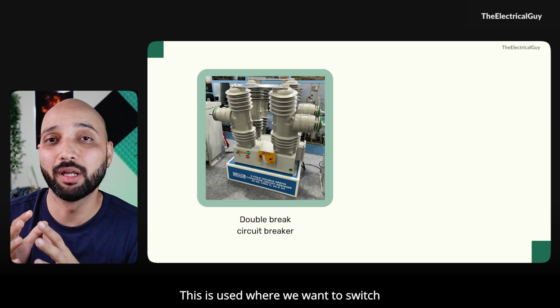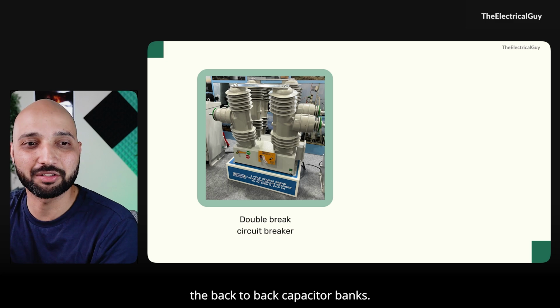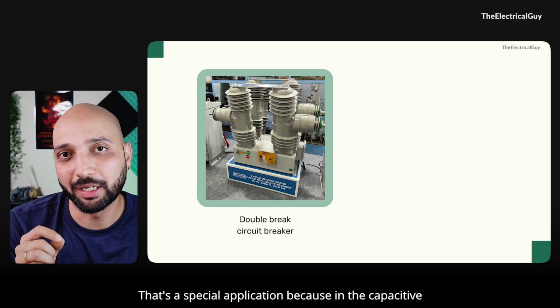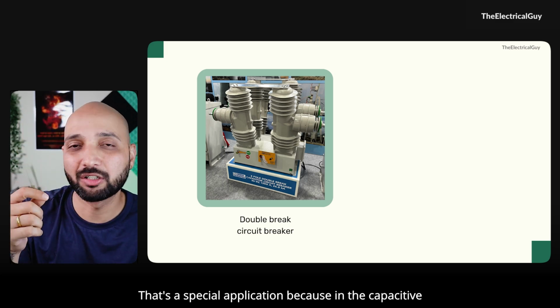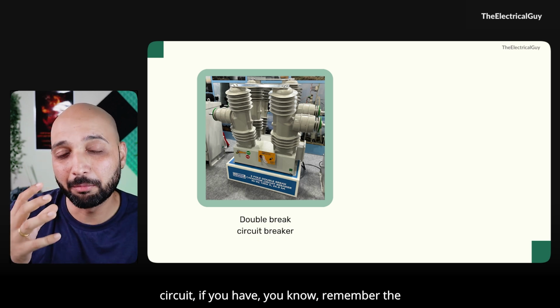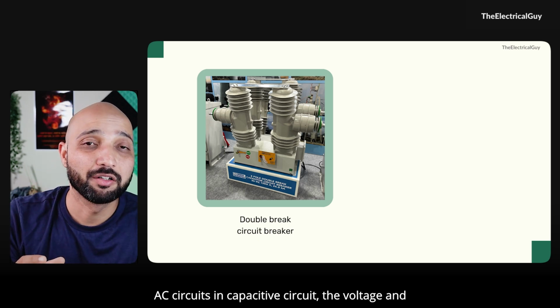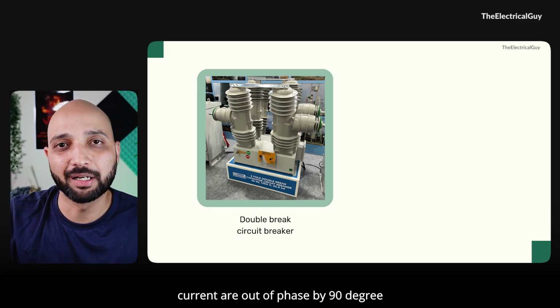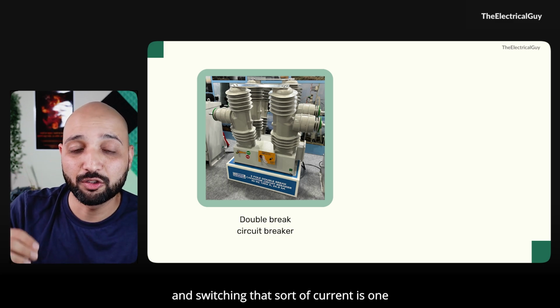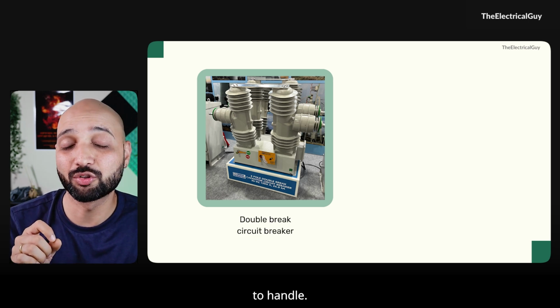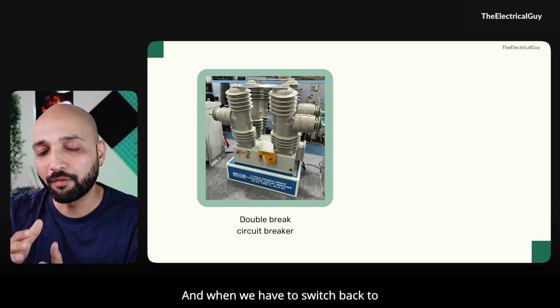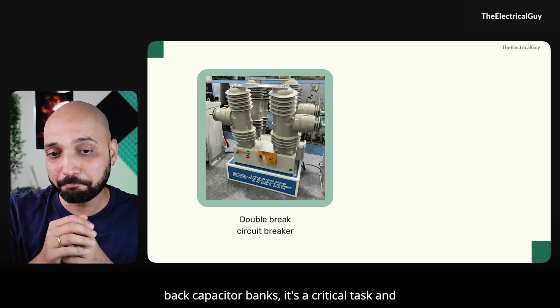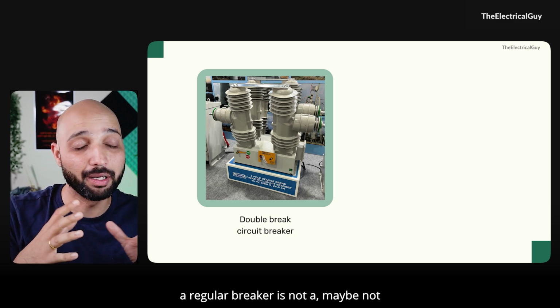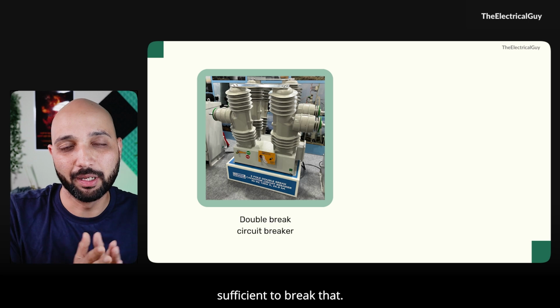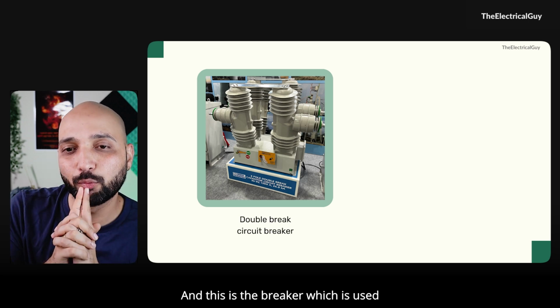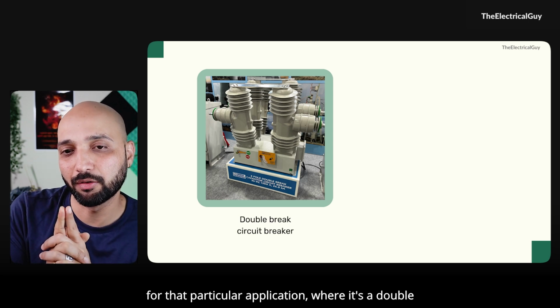This is used where we want to switch back-to-back capacitor banks. That's a special application, because in a capacitive circuit, remember, the voltage and current are out of phase by 90 degrees. Switching that sort of current is one of the critical activities a circuit breaker needs to handle. When switching back-to-back capacitor banks, it's a critical task, and a regular breaker may not be sufficient to break that.